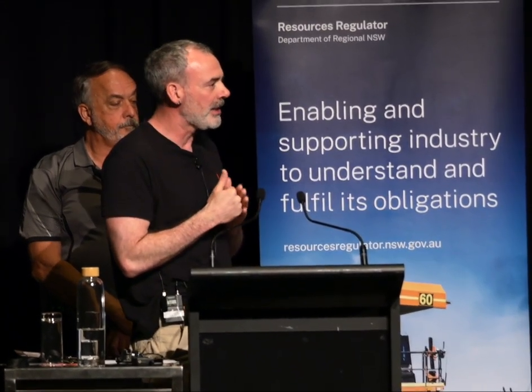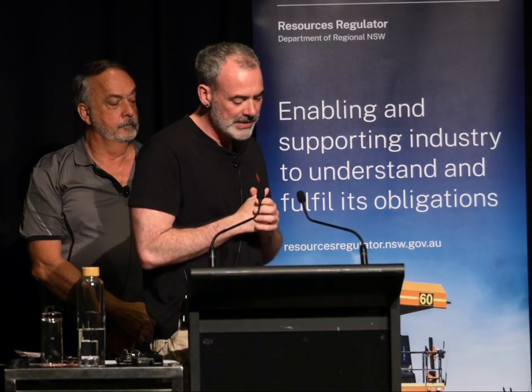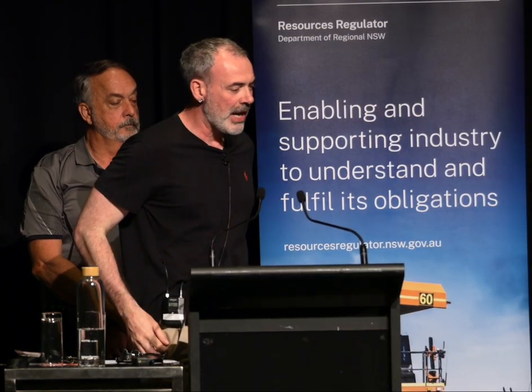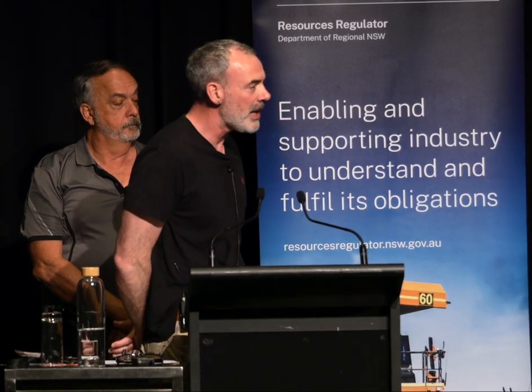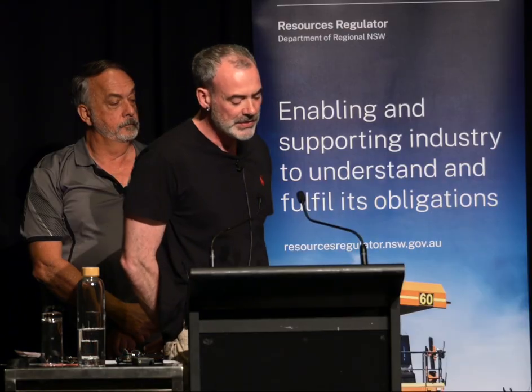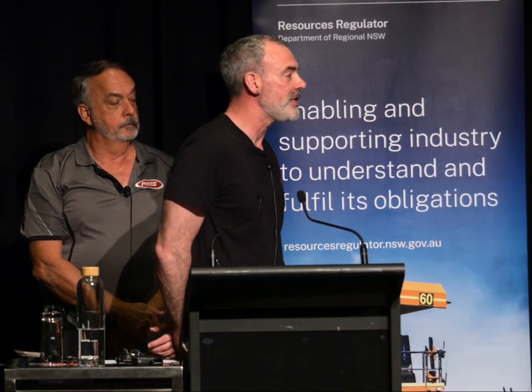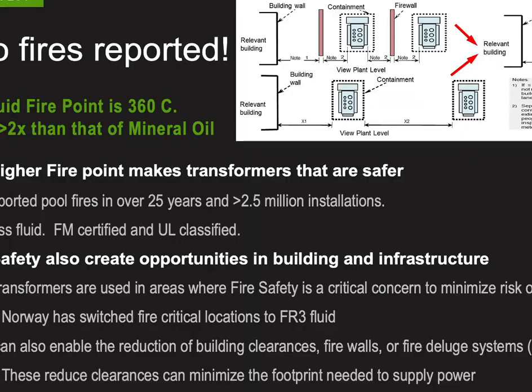I've seen some product, the natural ester by other manufacturers, being used in higher and higher voltage classes, so that's good as well. The test validation includes factory acceptance testing, also routine condition monitoring activities such as visual inspections, oil testing, electrical testing. And here in Australia, the transformer manufacturers use natural and synthetic esters in their transformers. I guess the challenge now as they become more popular is to educate asset managers about the operational differences, because ester fluids do in some ways behave in a different way to mineral oil.